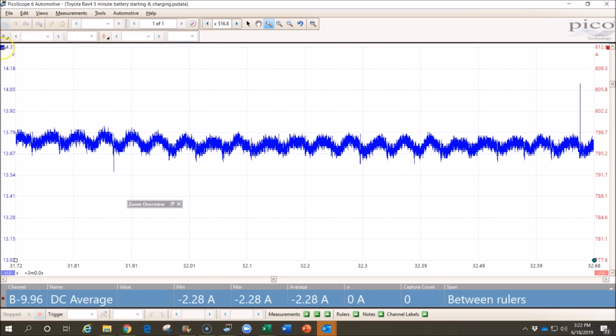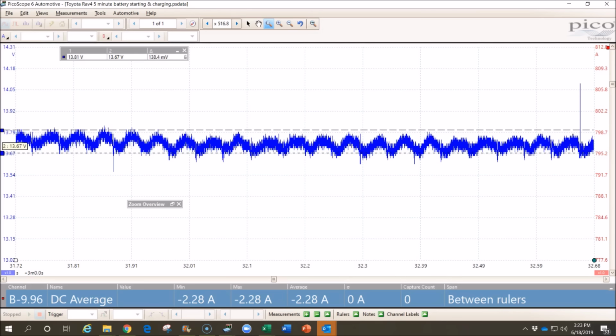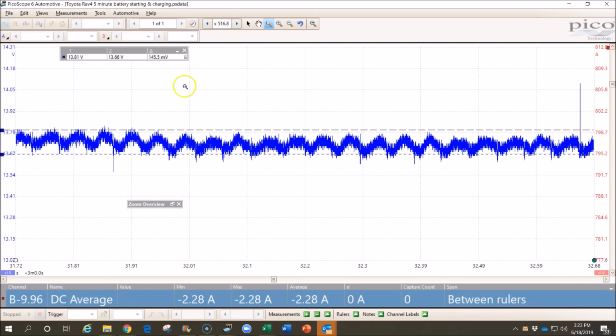As a rule of thumb, that ripple should never fluctuate more than about 250 millivolts. So let's come over here and measure the top to bottom of our ripple, just approximately, and check. We're at 145.5 millivolts. So that alternator ripple looks good.